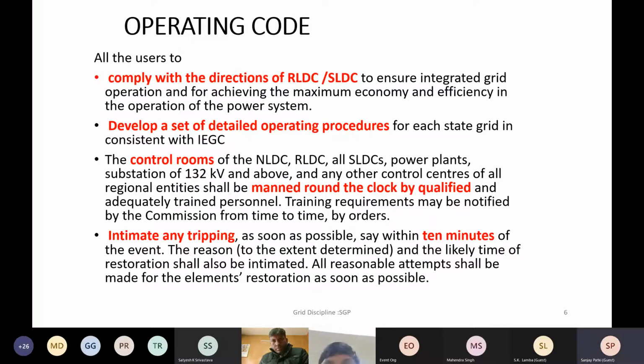So there is a grid code as a regulation, and its compliance is monitored by the load dispatch center. That is the role. Accordingly, they develop a set of detailed operating procedures, and the control rooms at various levels, at 132 kV and above, will ensure compliance to the directions given by NLDC, RLDC, and SLDC. At the same time, if any major event occurs at any location of the power station, the information has to be given to the load dispatch center immediately, so that appropriate actions can be initiated.